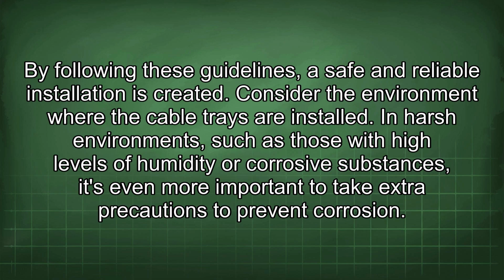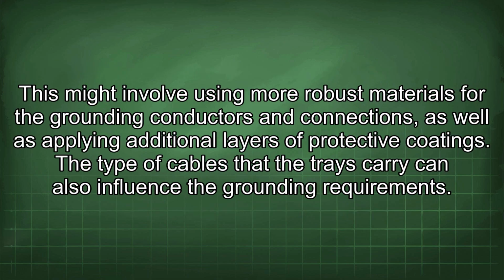Consider the environment where the cable trays are installed. In harsh environments, such as those with high levels of humidity or corrosive substances, it's even more important to take extra precautions to prevent corrosion. This might involve using more robust materials for the grounding conductors and connections, as well as applying additional layers of protective coatings. The type of cables that the trays carry can also influence the grounding requirements.